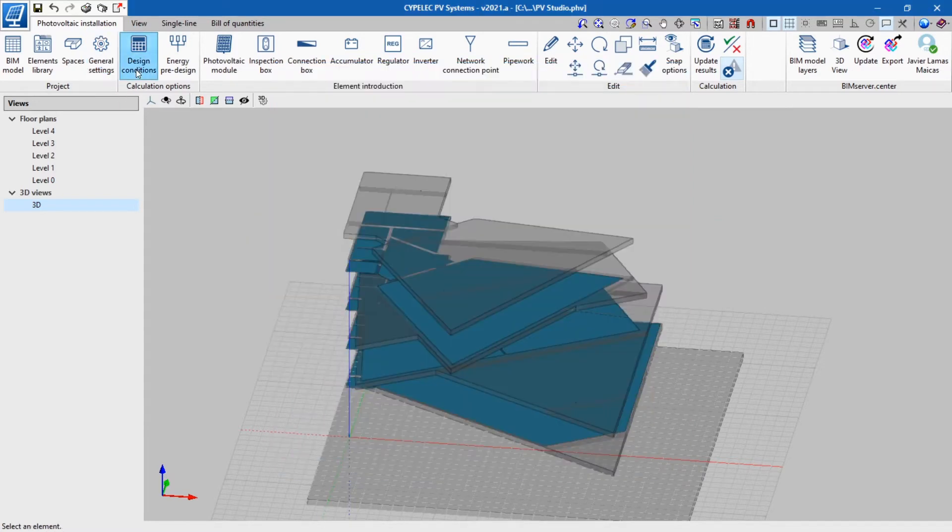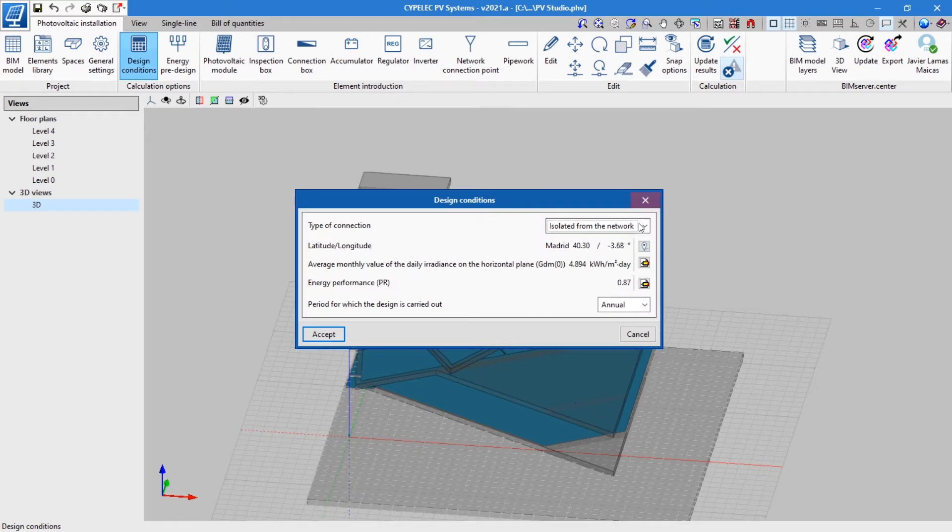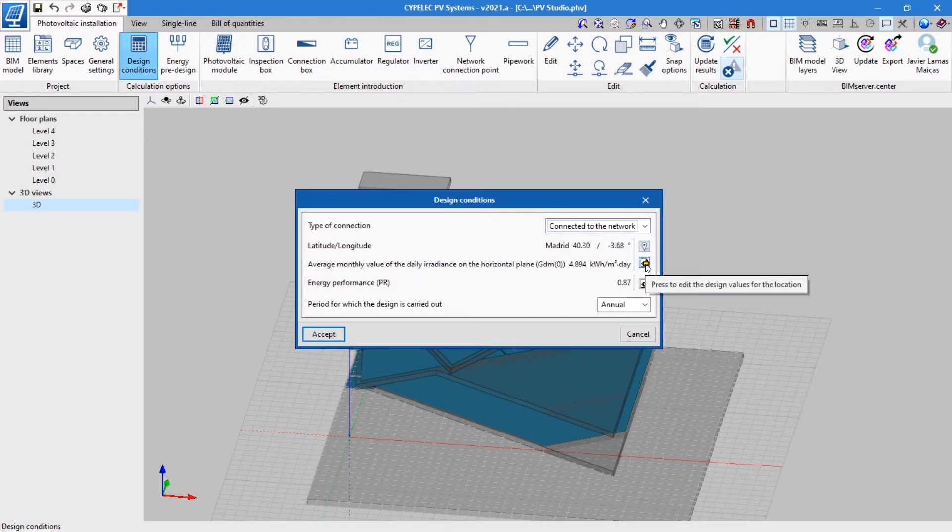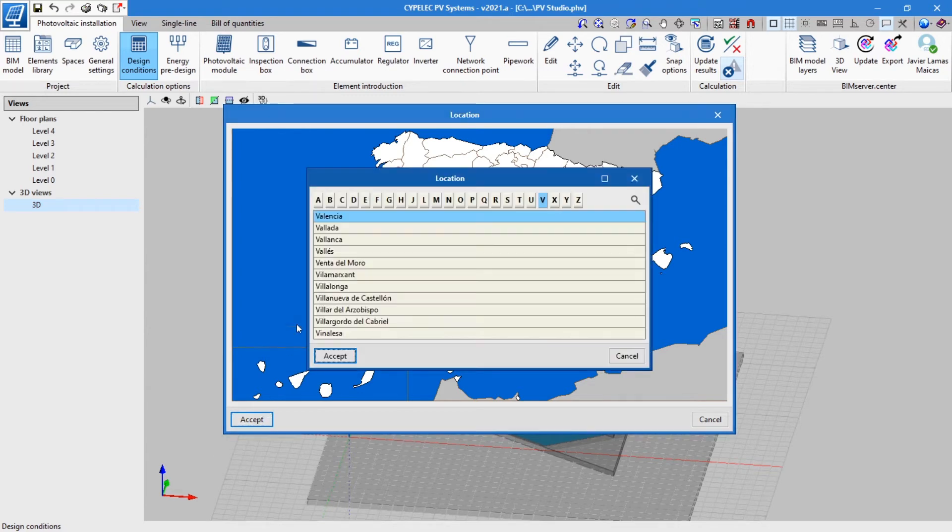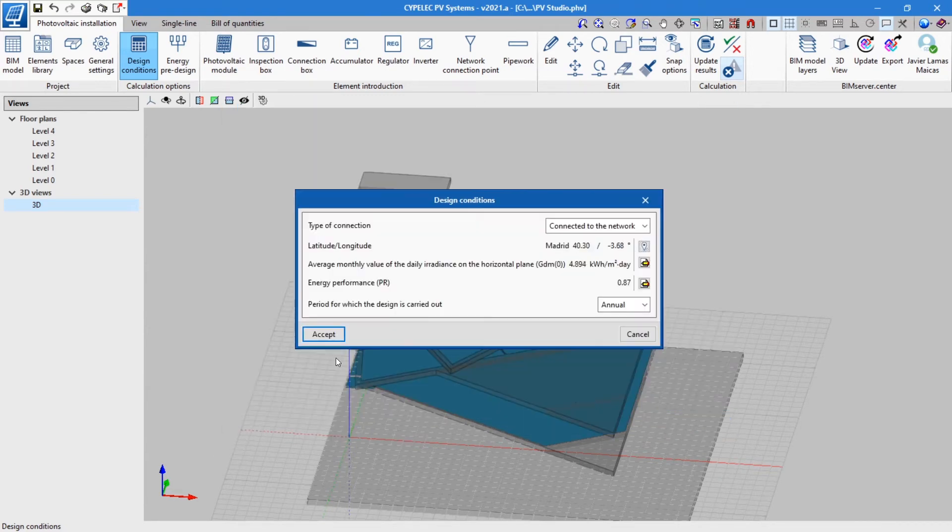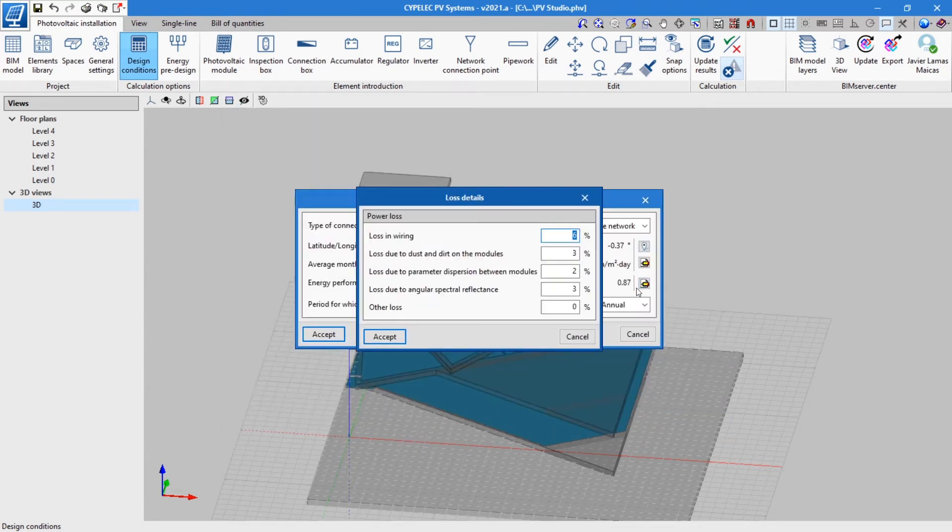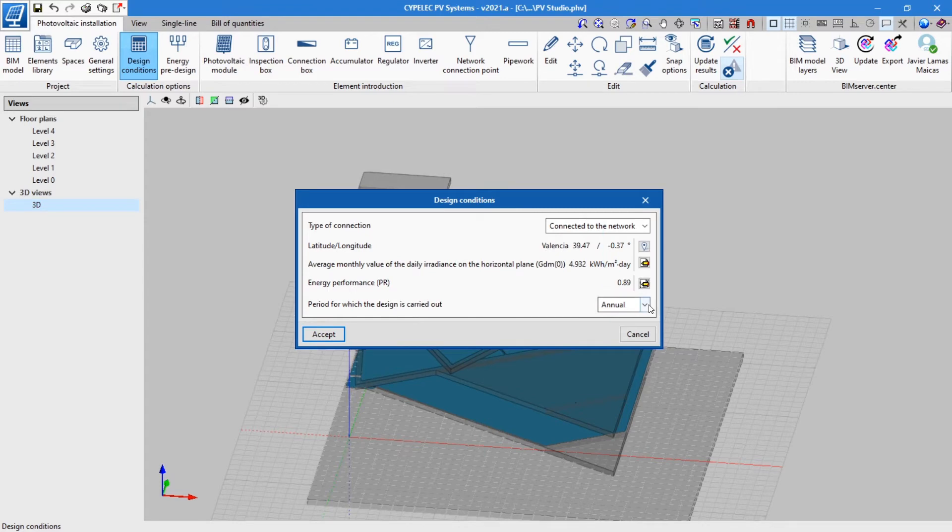The application makes it possible to configure the design conditions for the calculation. In this window, we select if the installation will be isolated or connected to the network. It also allows the building to be located by automatically reading the average monthly value of the daily irradiance. The performance of the installation will be calculated according to the losses entered, and it gives the option of choosing the period for which the design is carried out.